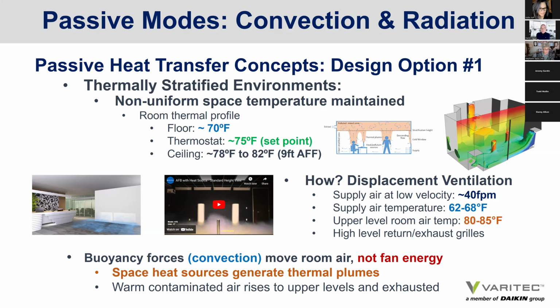You use displacement ventilation, a topic that I've been speaking to now for over 15 years, and we've had many successful installations. How does displacement ventilation work? You actually inject air at low velocity, not 150 feet per minute, but at 40 feet per minute. The air supplied is of a warmer temperature, not 55 degrees, but 62 to 68 degrees. And the upper level of a space could be anywhere from 80 to 85 or 78 to 82, as mentioned previously. And then that warm contaminated air in the space is exhausted from the room through return air grills that bring air back to the air handler or exhausted from the space.